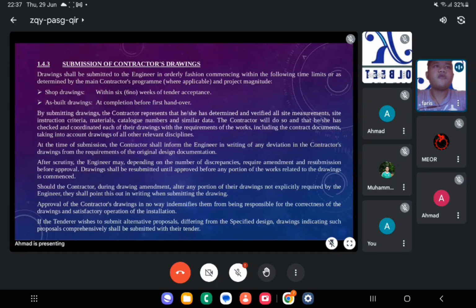1.4.3 Submission of contractor's drawings. Drawings shall be submitted to the engineer in orderly fashion, commencing within the following time limits or as determined by the main contractor's program (where applicable) and project magnitude. Number 1. Shop drawings within 6 weeks of tender acceptance. Number 2. As-built drawings at completion before first handover. By submitting drawings, the contractor represents that he or she has determined and verified all site measurements, site instruction criteria, materials, catalog numbers, and similar data.